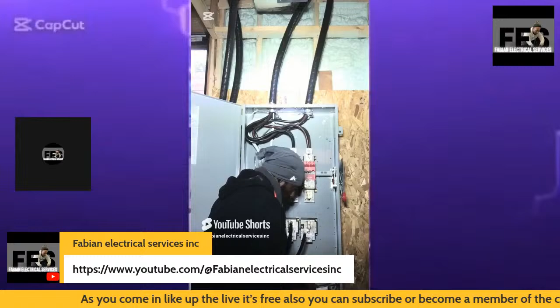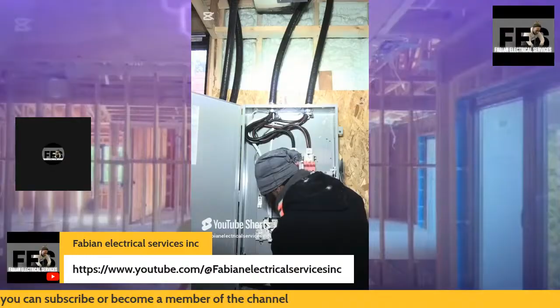You'll see me have the cables wired up into the lugs, the main disconnect, 400 amp disconnect service that I'm working with, and the cable I used was 250 kc mil parallel runs.